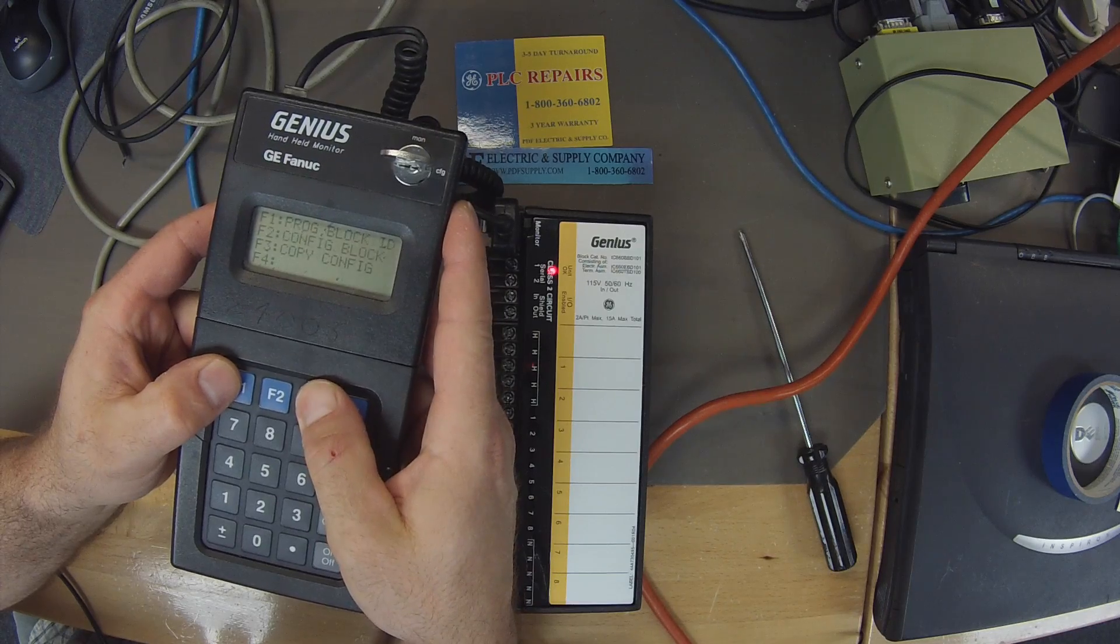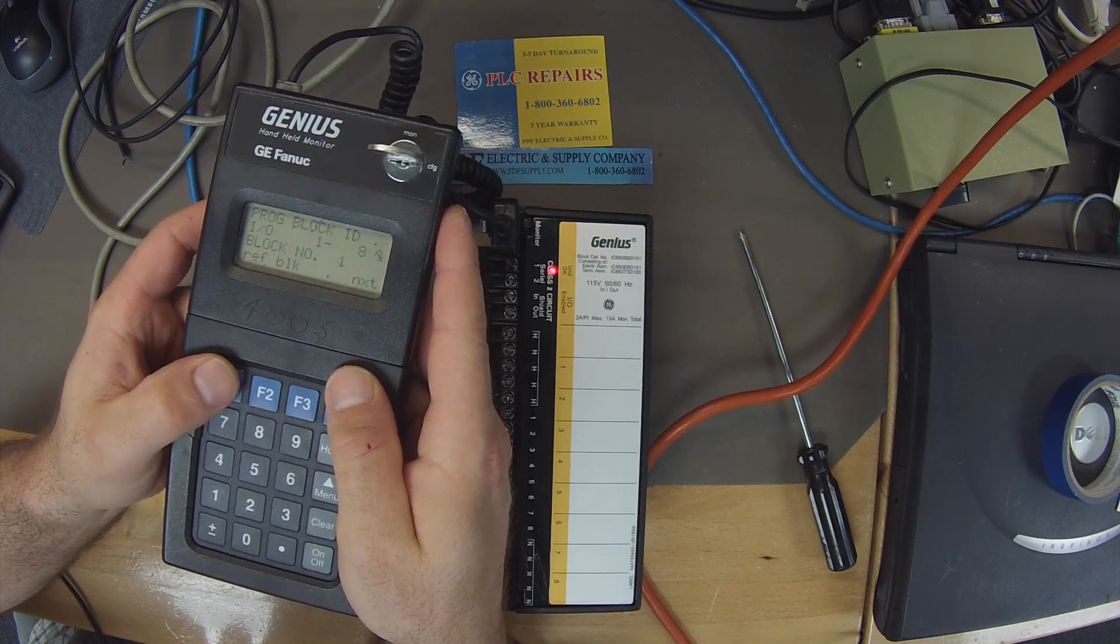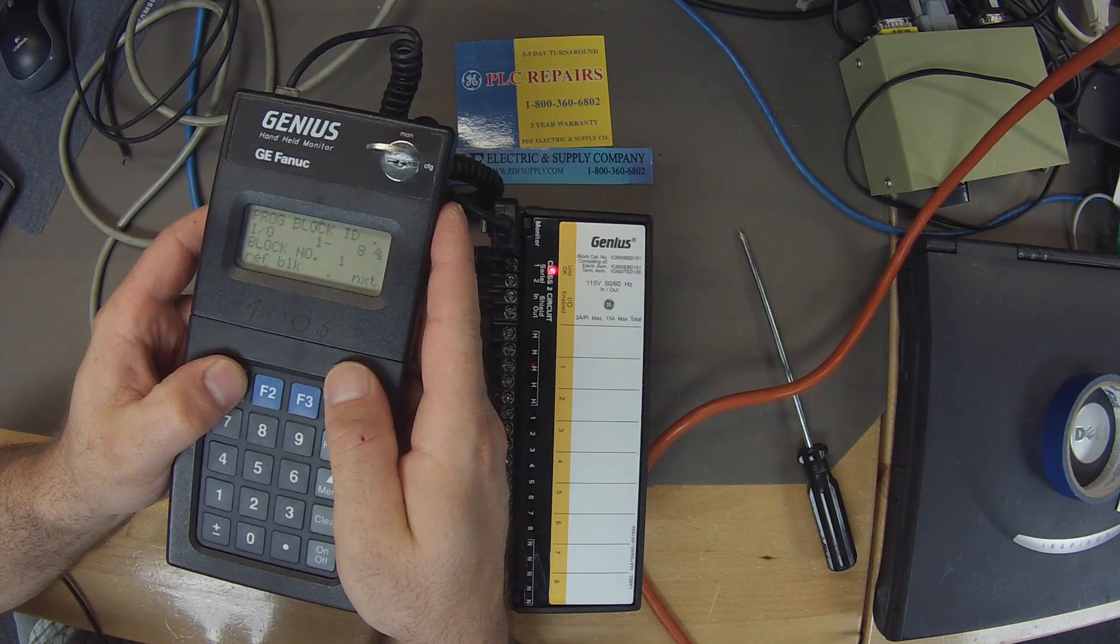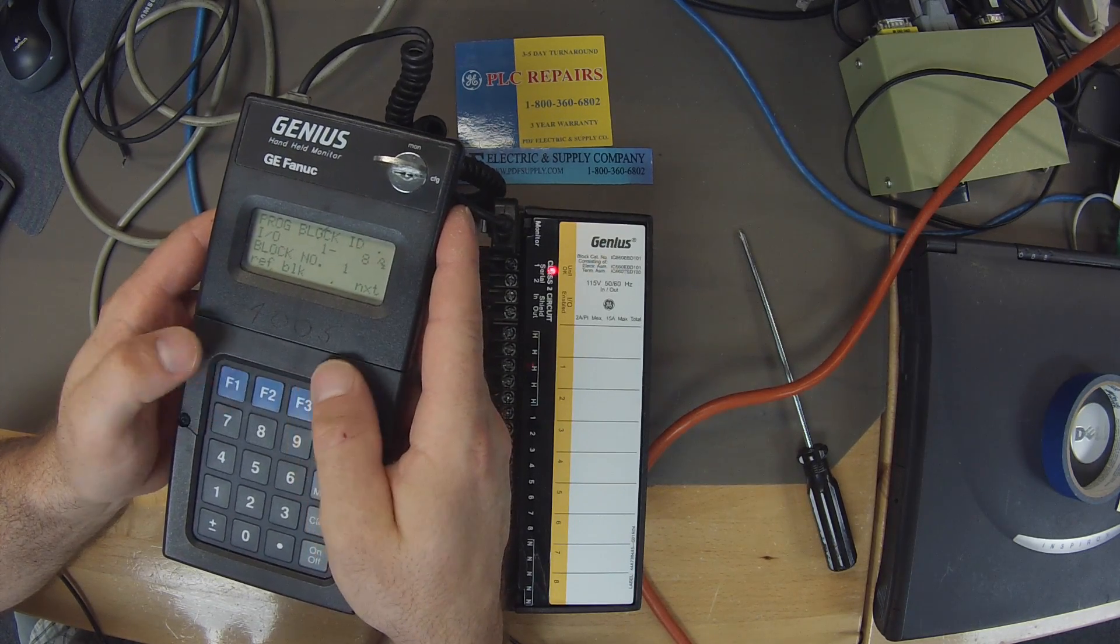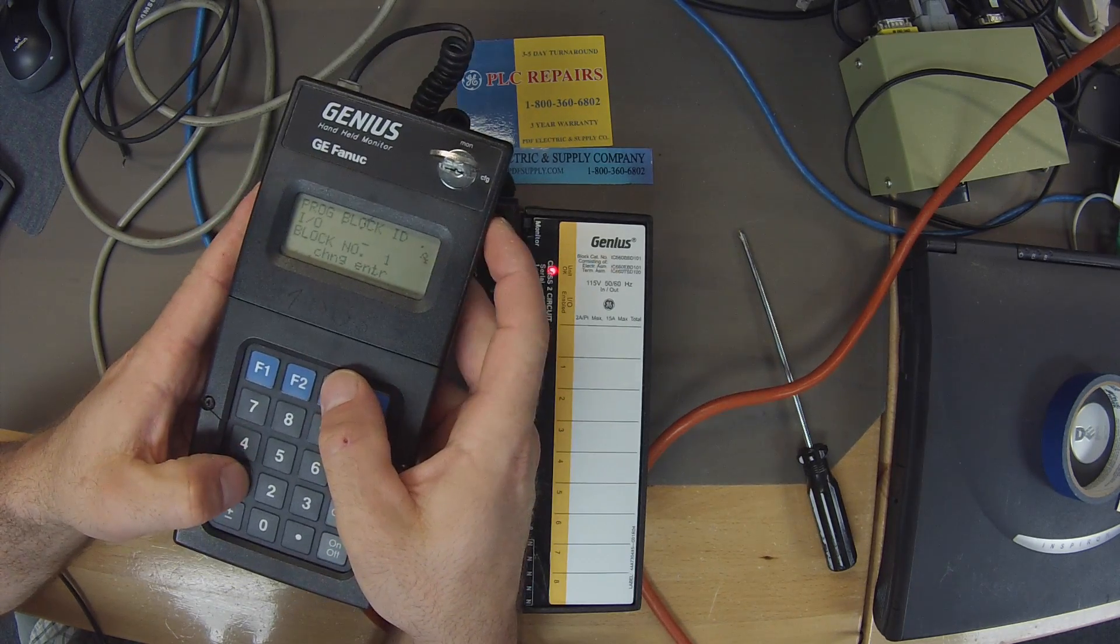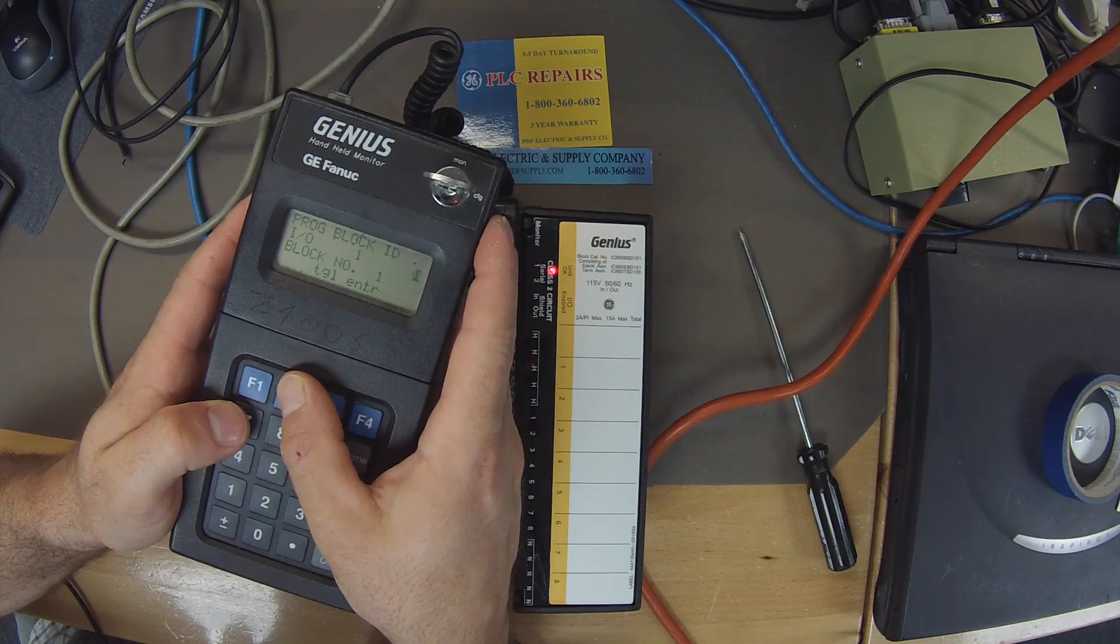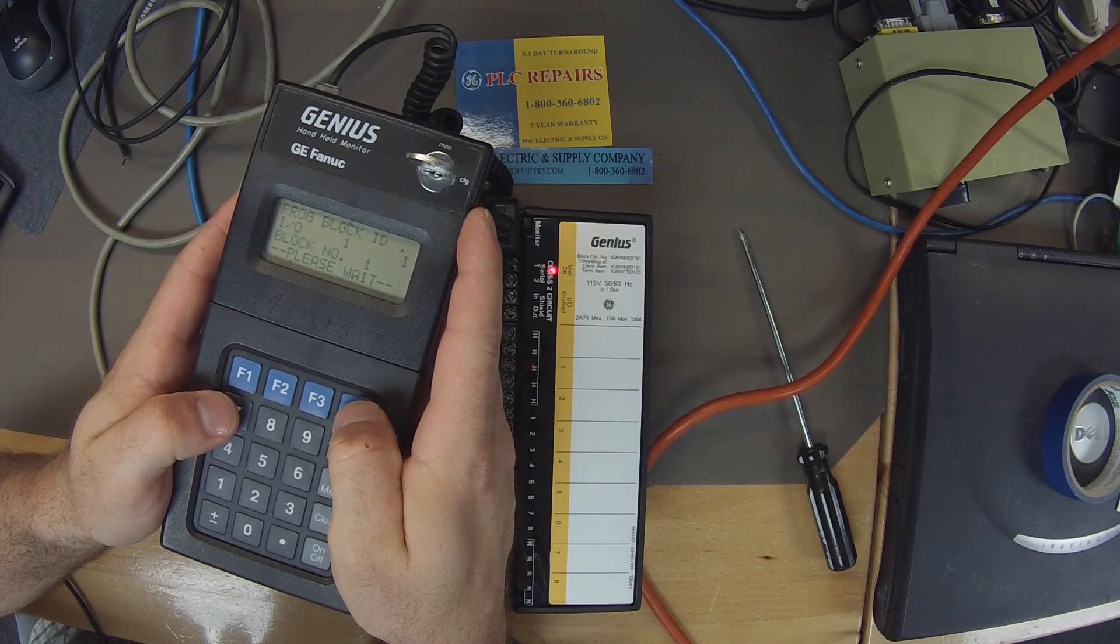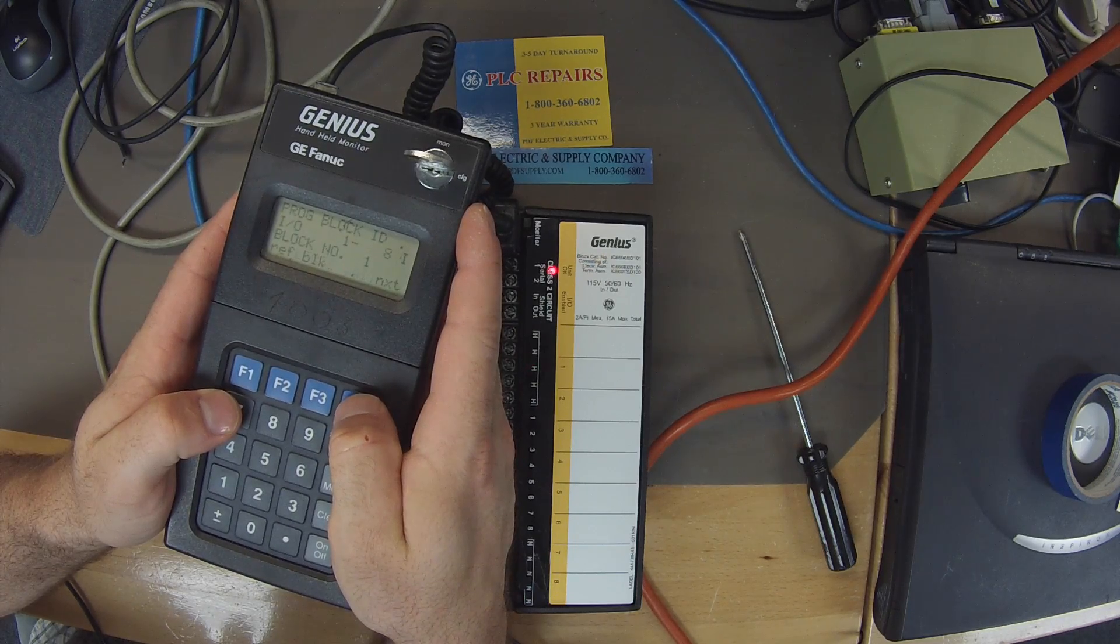I'm going to go back to home, configuration, F3, program block ID, F1. It's currently configured as input output 1 through 8 and it's block number 1. Block number 1 is fine to begin this test, but we're going to go to reference, F1, enter, 1, enter, and we're going to toggle this input output mode to just strictly input, and we're going to test the inputs first, so enter, and then it configures it.